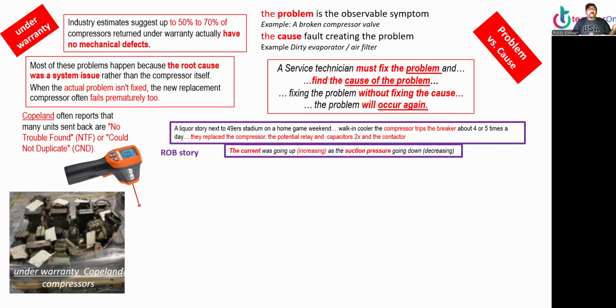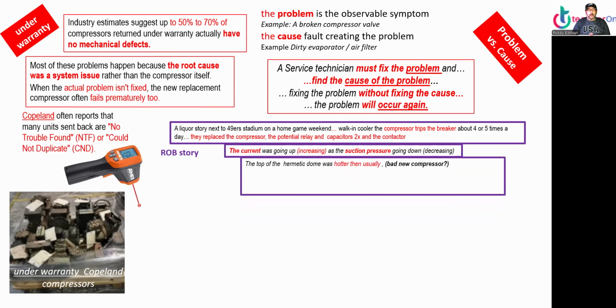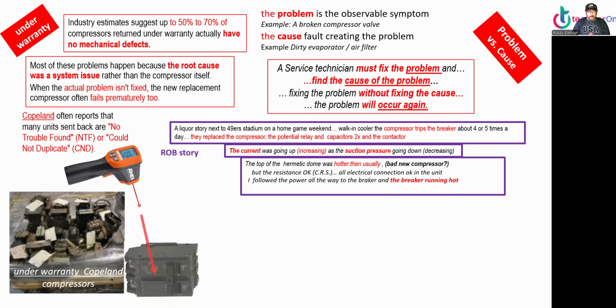The current was going up as the suction pressure was going down. So something's wrong. The top of the hermetic dome was hotter than usual. Is it a bad new compressor? I doubt it. But the resistance is okay. Common, run, and start is good. Electrical okay. I followed the power all the way to the breaker, and the breaker was running hot.